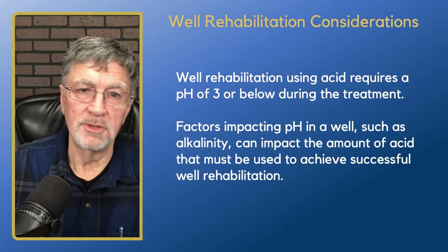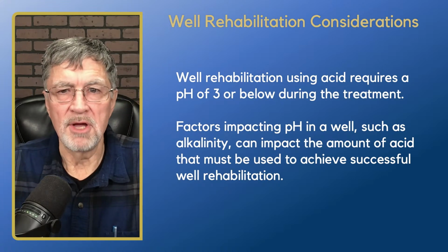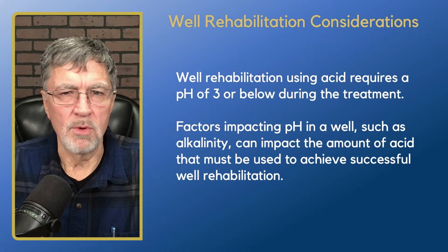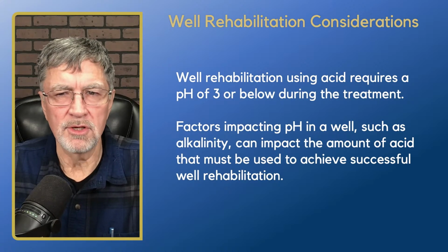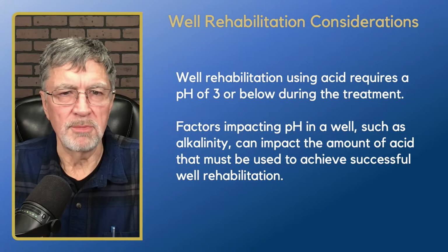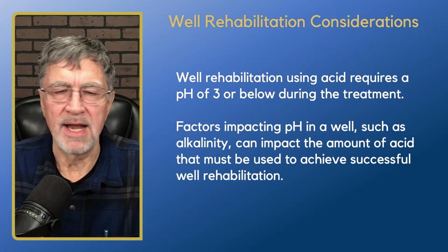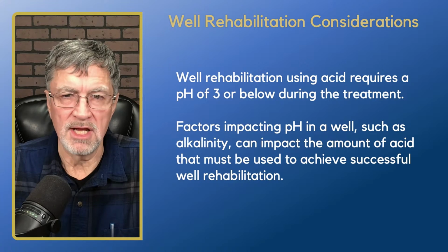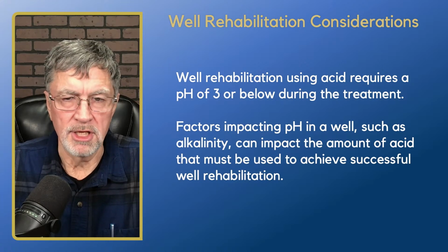All right, well rehabilitation considerations. Like I mentioned, well rehabilitation using acid generally is going to require maintaining a pH of 3 or below during treatment for optimal effect of that acid. So we're going to want to monitor and maintain that pH below 3.